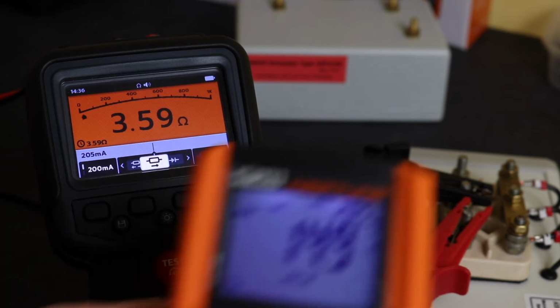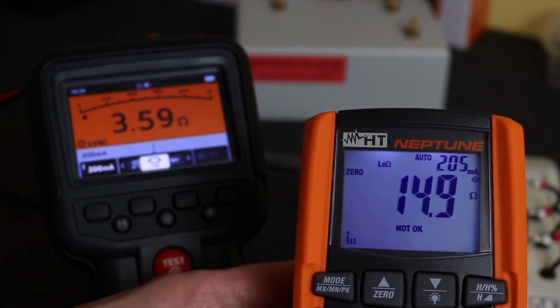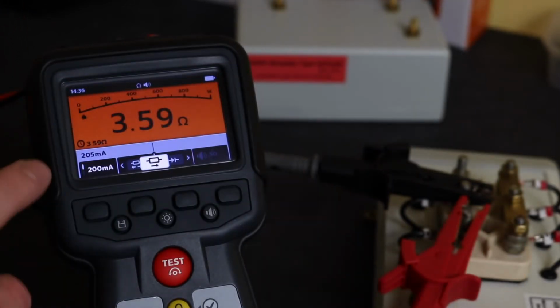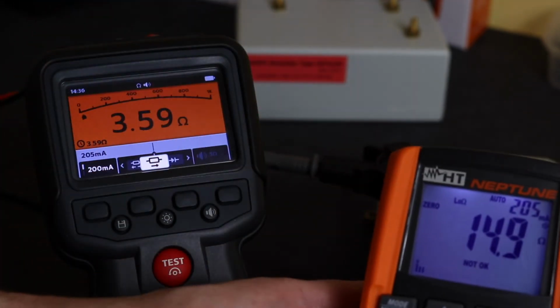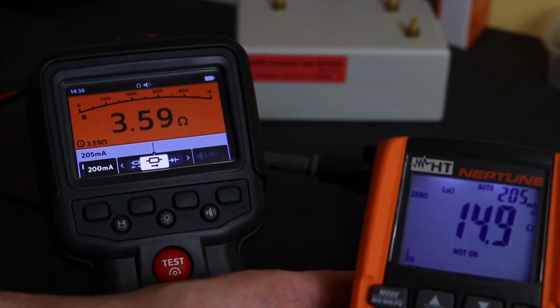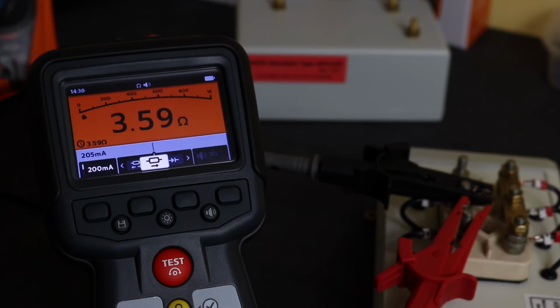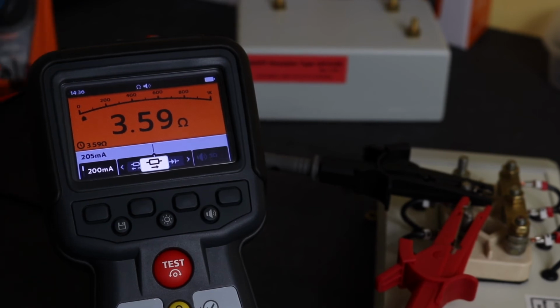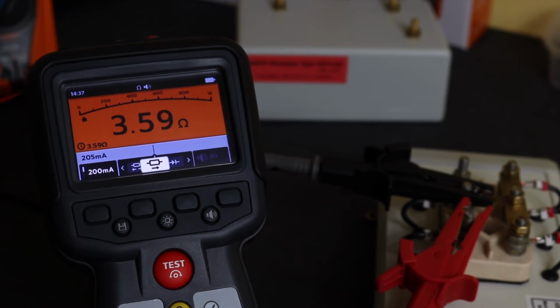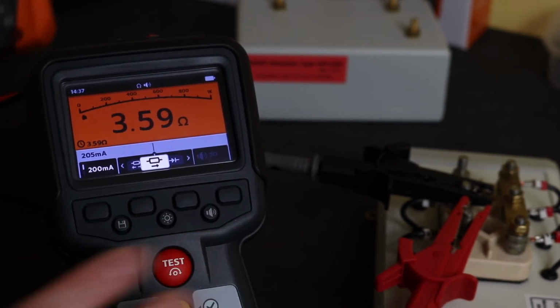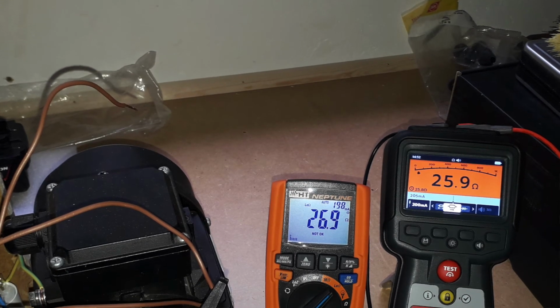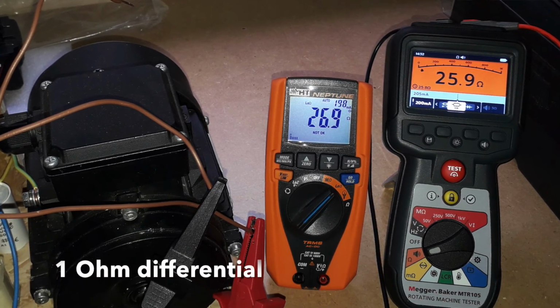And let's put that up against the 14.9. So we've got 205 milliamps on there, 205 milliamps on that. That's interesting. 205 milliamps test current on both of them, but this one reads correct. Something wrong with the Neptune there. Not sure. As I say, I do sometimes hit issues with 200 milliamp test currents on these instruments that have a lot of inductance in them. So what I need to do really is take this little Neptune out and measure some actual motors with it and see what that brings.